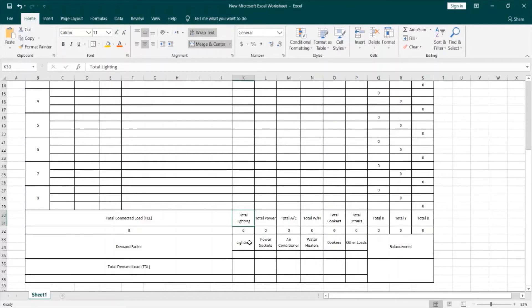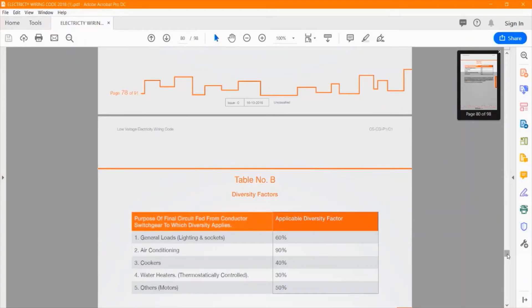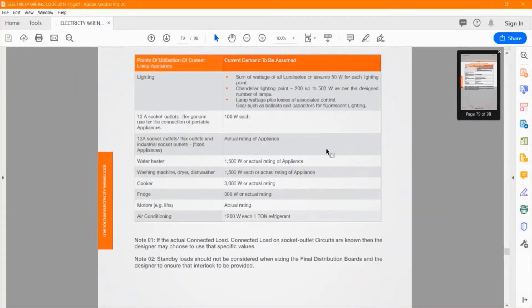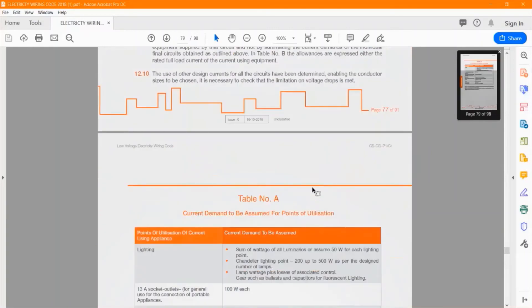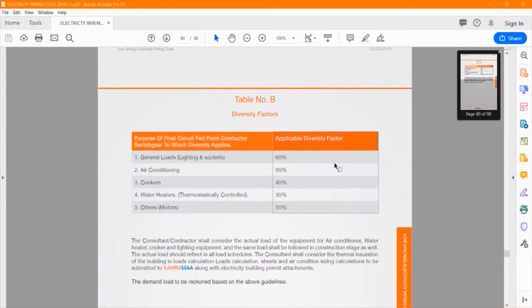However, demand and diversity factors may also be stated in your wiring code or electrical regulations of your country. For example, let's have a look at the wiring code of Qatar, which follows British standards. We will open the chapter for demand and diversity load — it's section 12. Looking at the table, which states the diversity factors in percentage for general loads, air conditioning, cookers, water heaters, and others, you will see that for general loads it's 60%, air conditioning 90%, and so on. This also depends from country to country — some countries have very high temperatures, so the demand for air conditioning will be much more than in other countries.